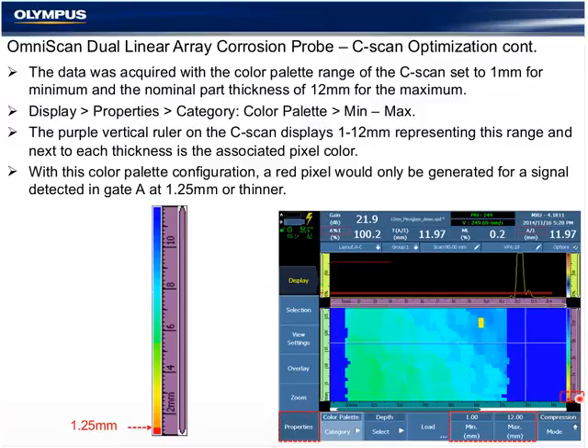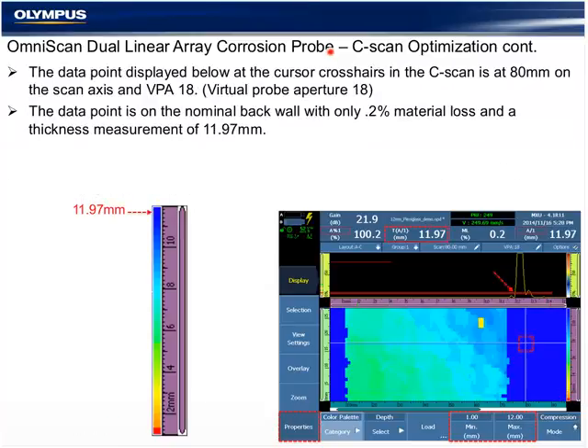As I adjust these numbers or move this on the touch screen of the instrument or with a mouse in OmniPC, the contrast of the C-scan is going to change to help me find the low points in the data or the problem areas of whatever I've just scanned. When I place the data cursor over an area here with no corrosion, I can see the 11.97 millimeter reading, which was taken at the leading edge of gate A here. It's a 0.2% material loss, and we can see the color associated with it is a dark blue.